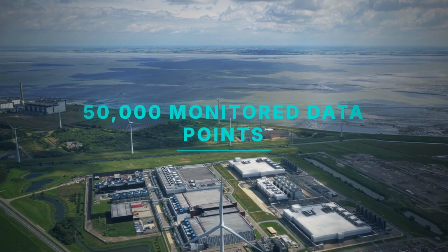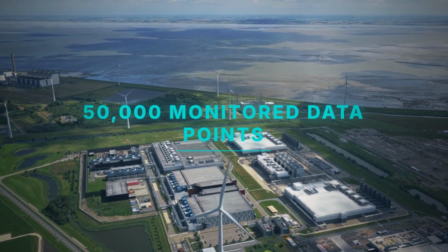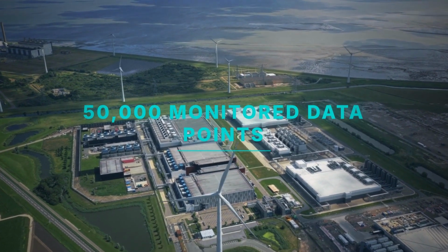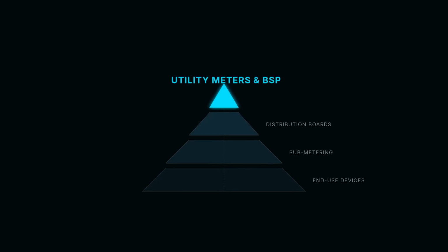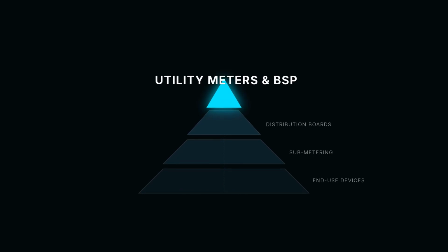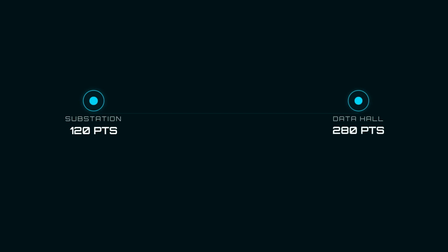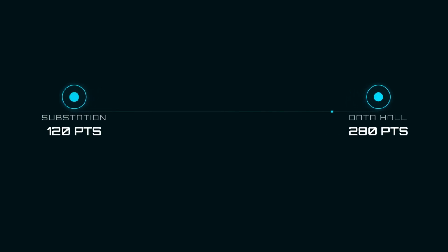FULCRUM. At FULCRUM, DCIM is not just an asset register, it is an operational intelligence platform. We monitor 50,000 data points across this 25-hectare campus, using AI to drive capacity and maintenance. The hierarchy runs from the utility fiscal meter at the BSP, measuring total campus energy for billing and carbon reporting. Every megawatt that enters the campus and every kilowatt that leaves a server rack is measured with total precision.